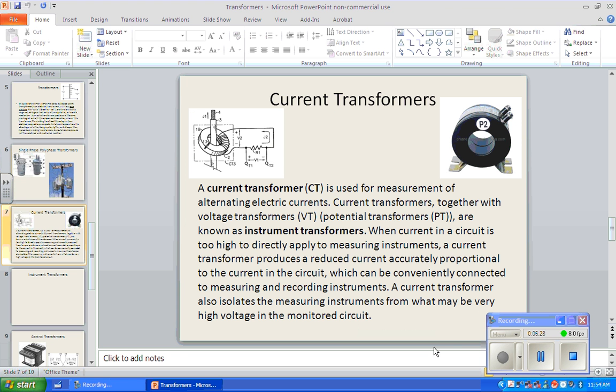Okay, current transformers, you've learned about them in the first semester, I hope. A current transformer is just a donut, so to speak, of wires that are wound very tightly. You run a single wire through it, and it infers the current in that by stepping that current down so that you can read it more safely. And what do we never do with a current transformer? Leave it open. Don't leave it disconnected and have current going through the wire that's going down through the middle of the donut, because you're going to be building up voltage potential and current potential, so that when you do touch them, you might get a really bad surprise. So it's one of the things we don't do with a current transformer is disconnect it.